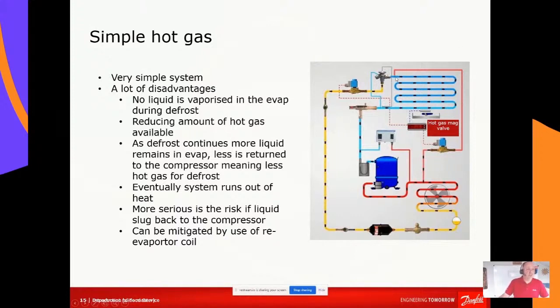It should really have a check valve, and then it will go through the evaporator heating the evaporator up and melting ice, frost, etc. The challenge is that's a one-to-one system, so we get a sort of ever-reducing amount of hot gas.